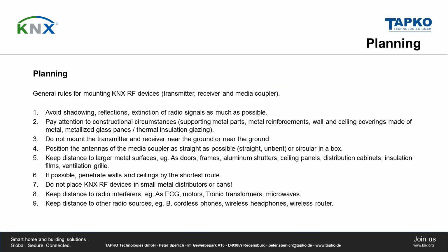So, general rules for the planning. Avoid reflections. It will extinct the radio signal. You have to think about the construction circumstances, for example, if you have floor heating systems, or a lot of steel in the concrete, in the ceiling or in the floor. Do not install KNX devices directly on metal plates or something like that. This might be very clear.